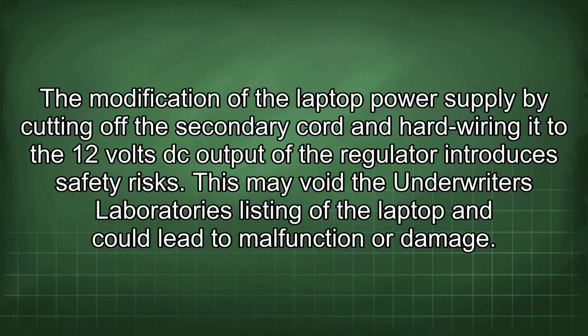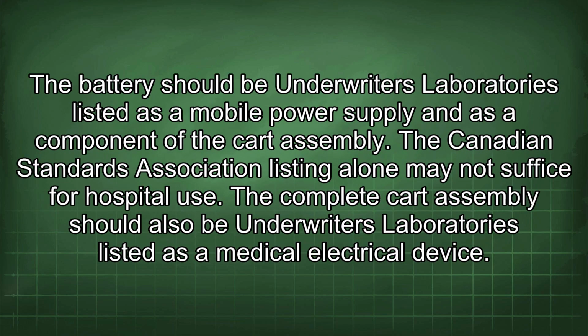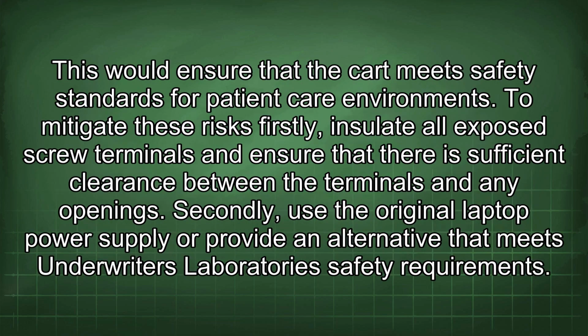This may void the Underwriters Laboratories listing of the laptop and could lead to malfunction or damage. The battery should be Underwriters Laboratories listed as a mobile power supply and as a component of the cart assembly. The Canadian Standards Association listing alone may not suffice for hospital use. The complete cart assembly should also be Underwriters Laboratories listed as a medical electrical device. This would ensure that the cart meets safety standards for patient care environments.